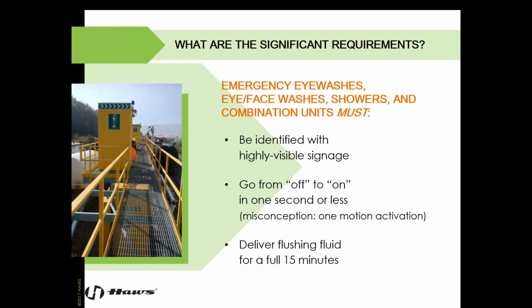So specific to products like a faucet-mounted eye wash, where it would require you to turn on your water source and then either twist, activate, or turn on the eye wash, that is a two motion, but that is approved by the ANSI standard as long as it's in 1 second or less. So keep an eye out for that.